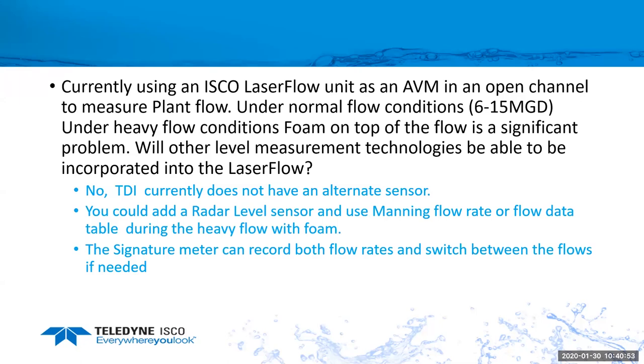Next question is, a customer is currently using the laser flow area velocity flow meter. Under normal flow conditions, they get 6 to 15 MGD. Under heavy flow conditions, they are developing foam on top of the water, which could create problems because the laser flow sensor uses the ultrasonic sensor for level, and if it cannot penetrate the foam, it's going to go into error. So an option for that is that you could install a bubbler again, or use a radar level sensor, and then with the Signature flow meter, we could have it switch over to the other technology. So what we could do is develop a flow rating curve, a level-to-flow curve, off of the laser flow sensor, and then we could switch over to using the level of the bubbler or radar sensor when you do have the heavy foaming conditions.